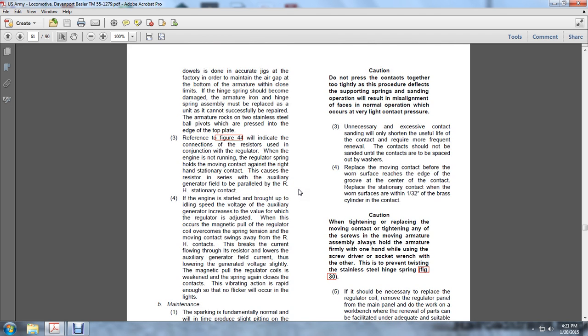Caution: do not press the contacts together too tightly, as they will deflect the supporting springs, and the sanding operation will result in misalignment. Normal operation occurs with very light contact pressure. Unnecessary, excessive contact sanding will only shorten the life of the contact. Frequent renewal of the contact should be avoided. Replace the moving contact before the worn surface first reaches the edge of the groove in the center of the contact. Replace the stationary contact when the worn surfaces are within 1/32 of an inch of the brass cylinder in the contact.